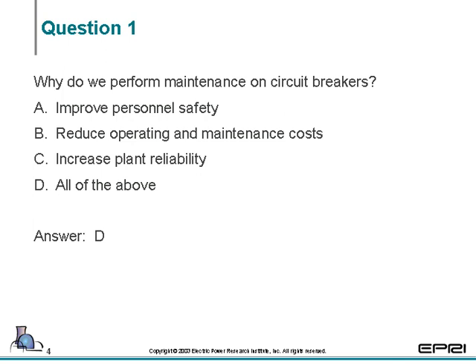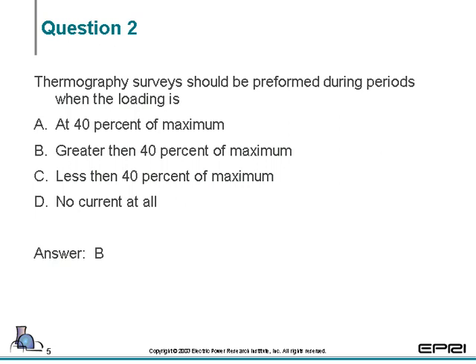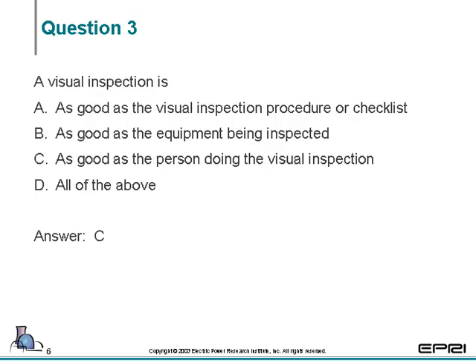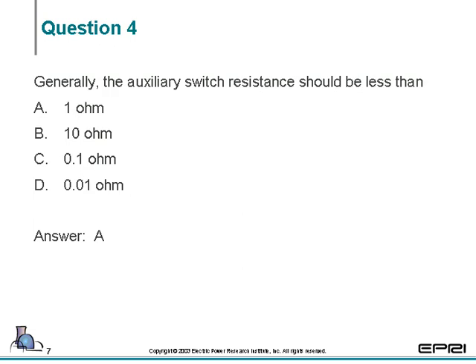Question 1, why do we perform maintenance on circuit breakers? The answer is D, all of the above. To improve personnel safety, we reduce operating and maintenance costs, and we increase the plant reliability. All very important and all correct. So the answer is D. Question 2, thermography surveys should be performed during periods when loading is, the answer is B, greater than 40% of maximum. If you just think about that, you'll understand why you need a greater load to detect the heating there. Question 3, a visual inspection is, answer is C, as good as the person doing the visual inspection. You need to have a person that's knowledgeable with the breaker and knowledgeable about what can go wrong with the breaker. So you need a qualified individual that's inspecting the breaker.